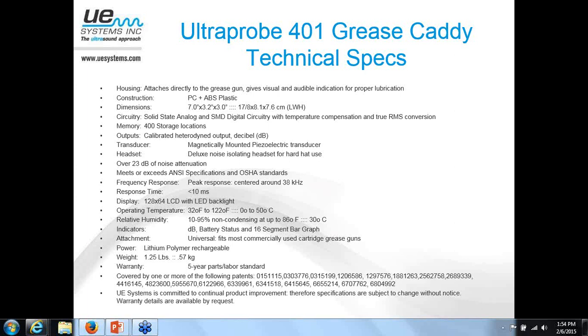But can you use this digital Ultraprobe as part of an ongoing lubrication management program on a monthly basis? Yeah, and that's exactly what it's designed for. It's designed for people to move away from simply time-based lubrication, which tends to lead to over-lubricating, and move more towards condition-based lubrication. And again, the simple concept is just friction. So when we have a bearing that's in need of grease, we've got a slight increase in the decibel level. What we're hoping to see is that when we're watching the decibel level and applying that grease, it's going to drop back down to a more normal baseline or steady level, and then we stop greasing.